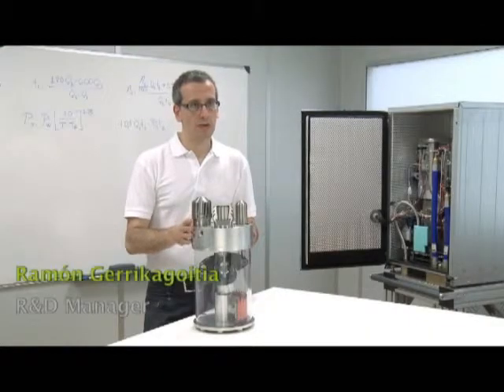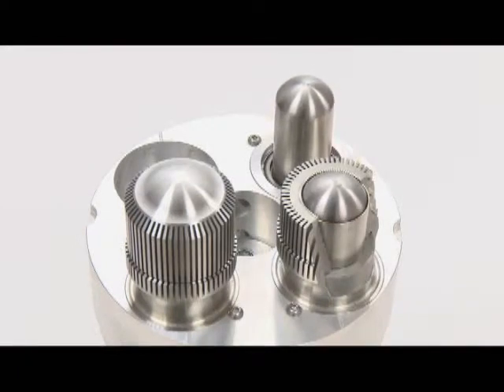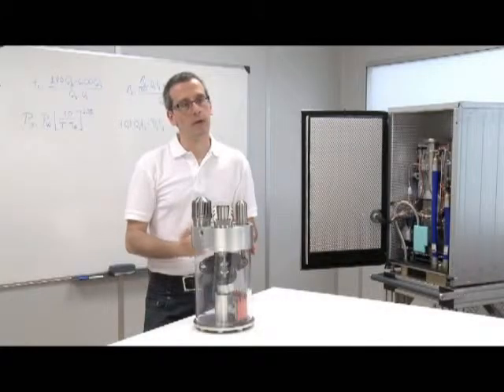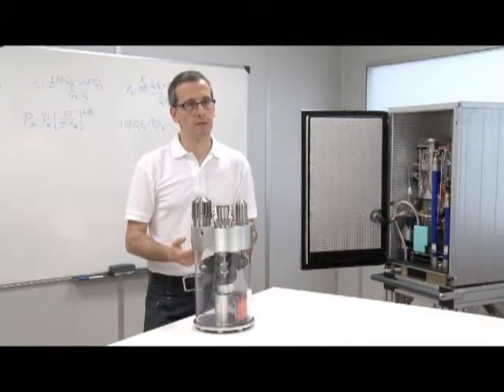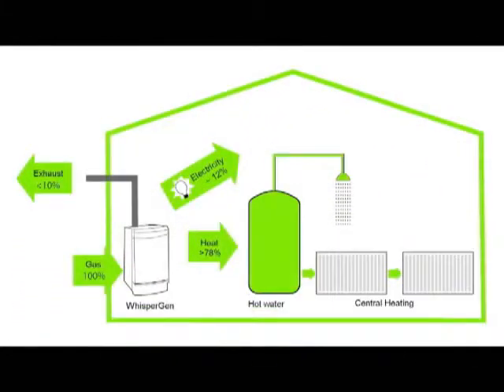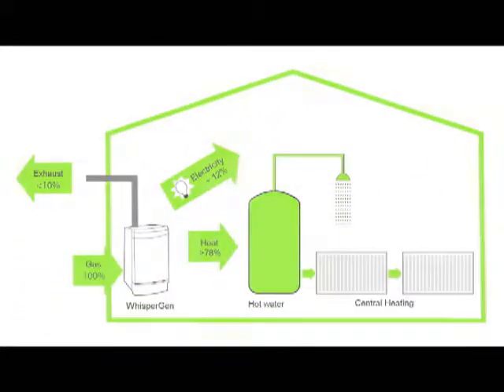The longitudinal movement of the pistons is caused by the nitrogen inside them expanding and being compressed. It expands due to the heat generated in the combustion chamber, and it is then compressed, making cold water circulate around the lower part. This water is then used to generate domestic hot water and for heating.